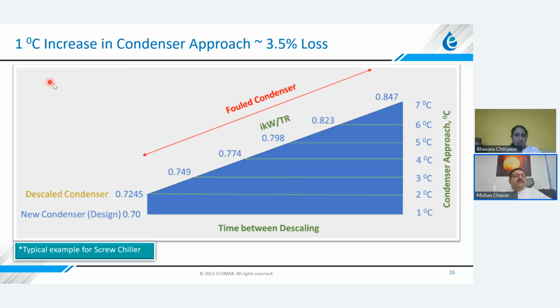Now, this is a typical example for a screw chiller. Here, I'm trying to explain how an increase in the condenser approach affects your kilowatt per ton, IKW per TR, in the fouled condenser. Now, here, if you see, when the condenser is new, the approach is about 1 degree C, and the IKW per TR is 0.7. As the approach increases, your IKW per TR goes up, right, up to here. And in many industries, we see 5 to 7 is a normal condenser approach when the condenser is fouled, okay?